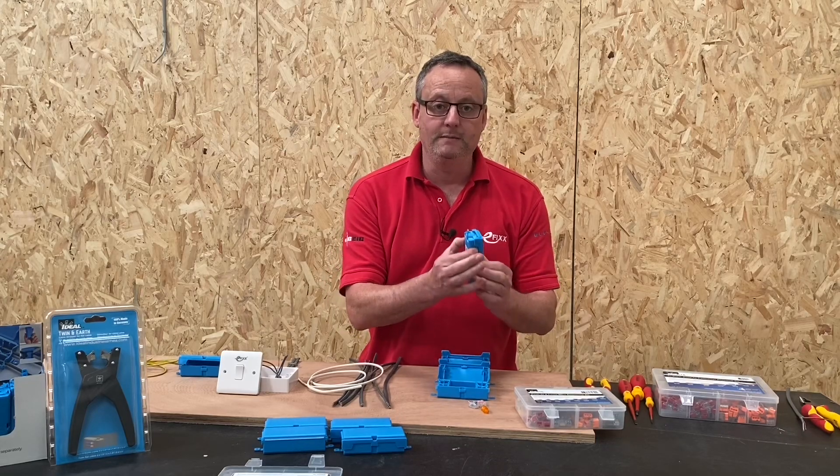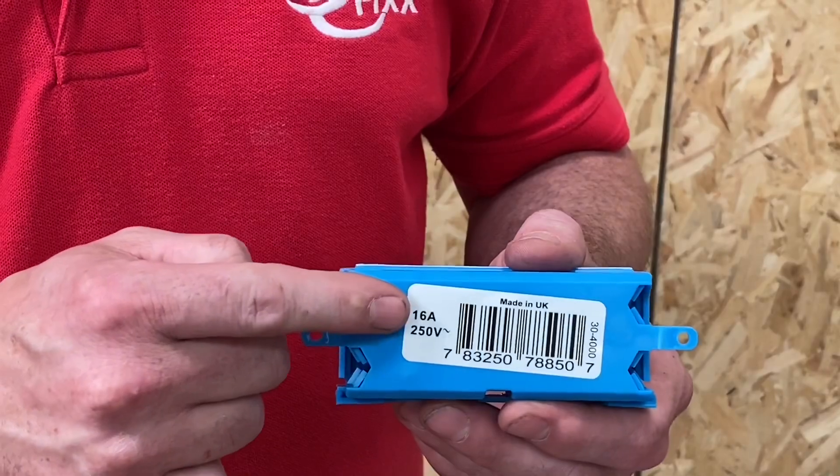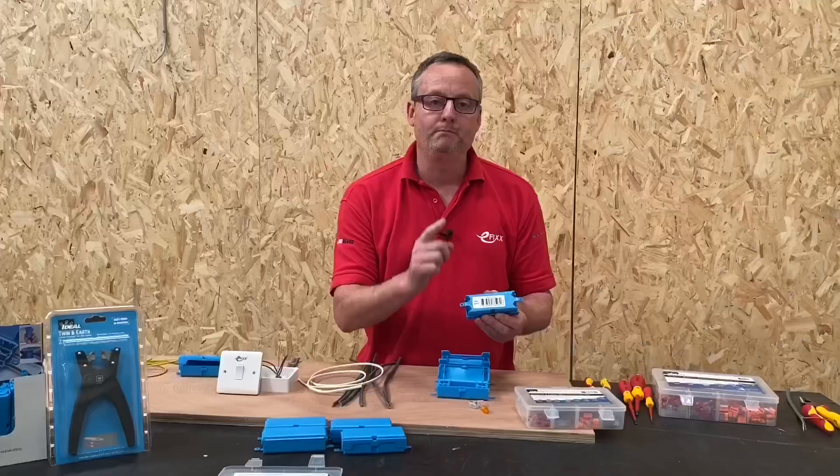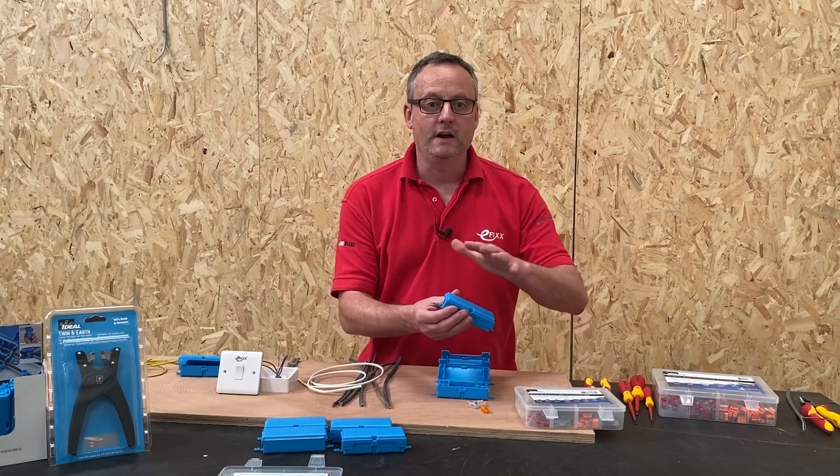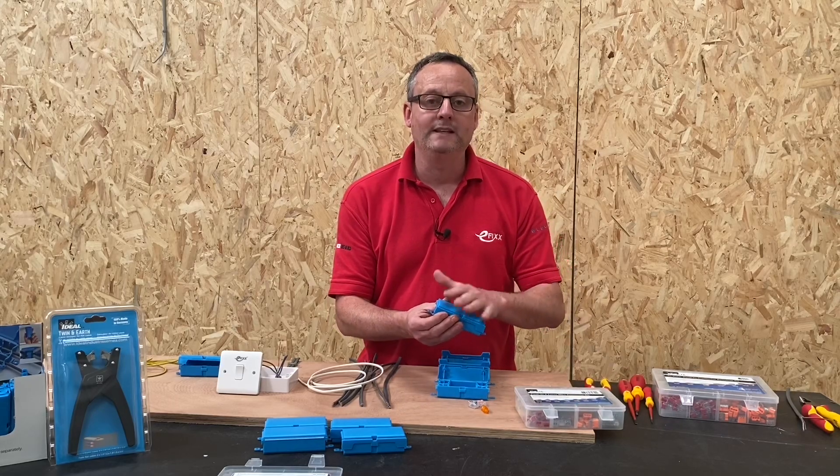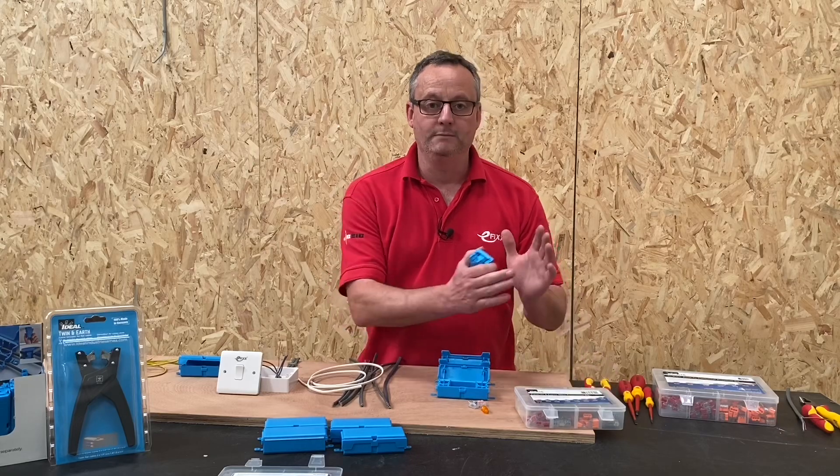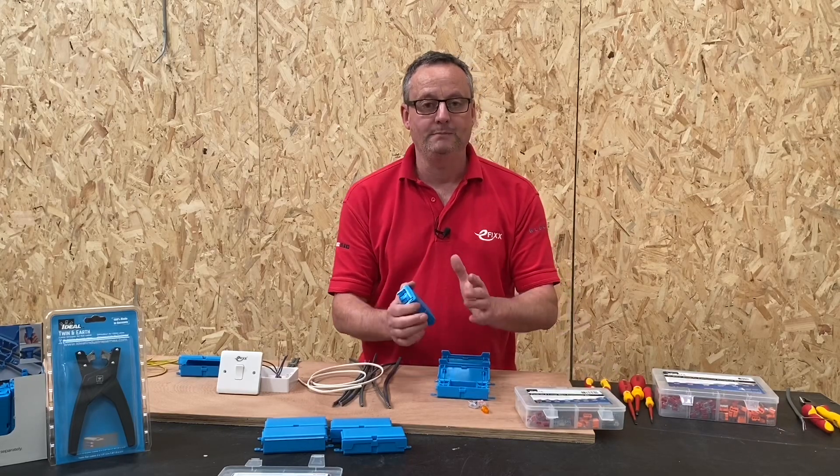It's designed to go through a 50 millimeter hole, and on the back it's rated at 16 amps. That's really important. It means whichever of the connectors we've just discussed we insert within this box, they are only rated at 16 amps.